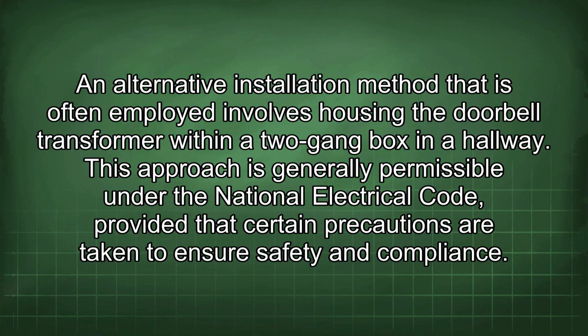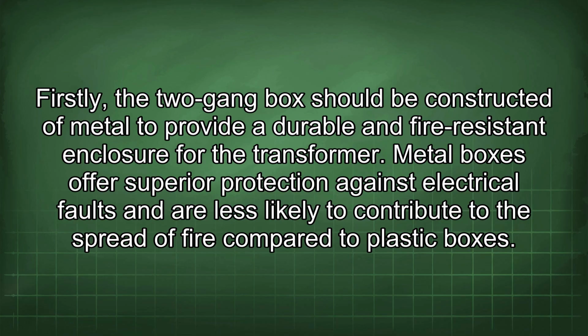An alternative installation method that is often employed involves housing the doorbell transformer within a two-gang box in a hallway. This approach is generally permissible under the National Electrical Code, provided that certain precautions are taken to ensure safety and compliance. Firstly, the two-gang box should be constructed of metal to provide a durable and fire-resistant enclosure for the transformer. Metal boxes offer superior protection against electrical faults and are less likely to contribute to the spread of fire compared to plastic boxes.